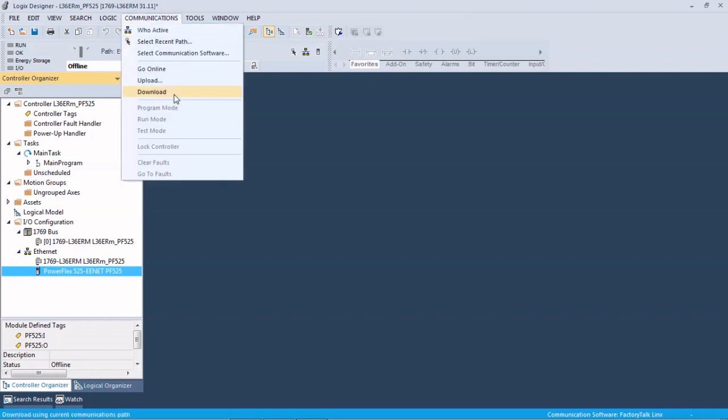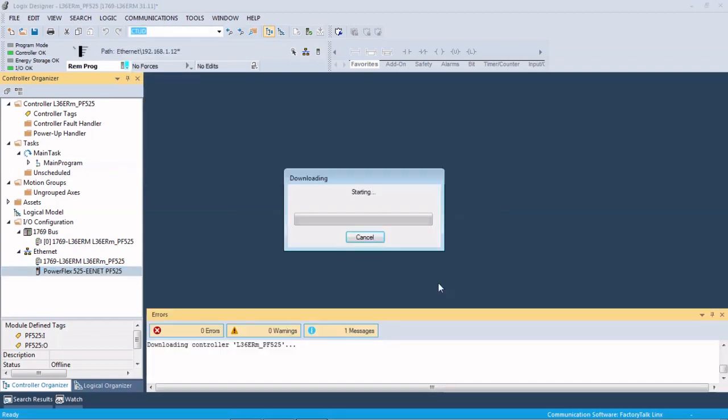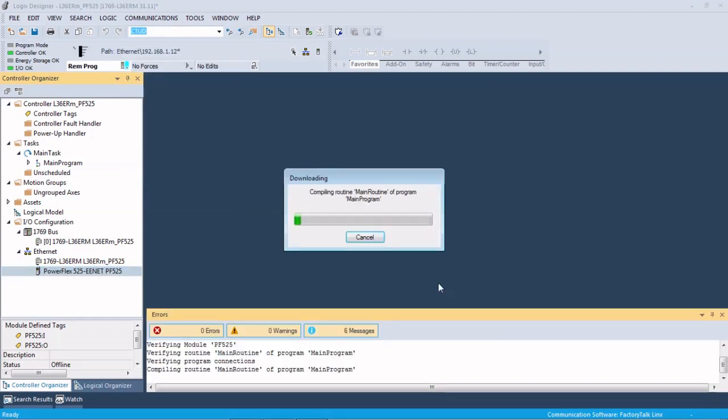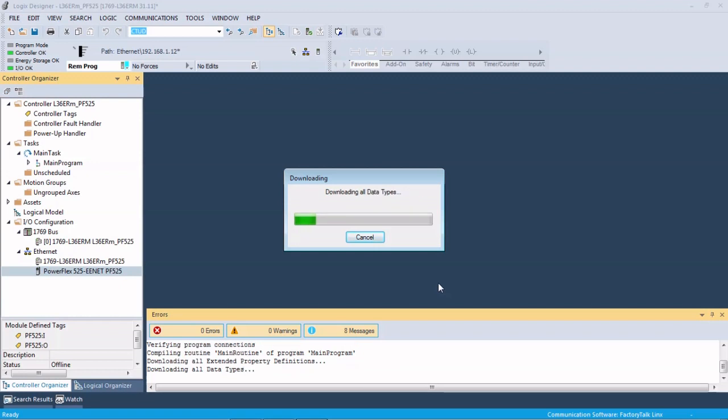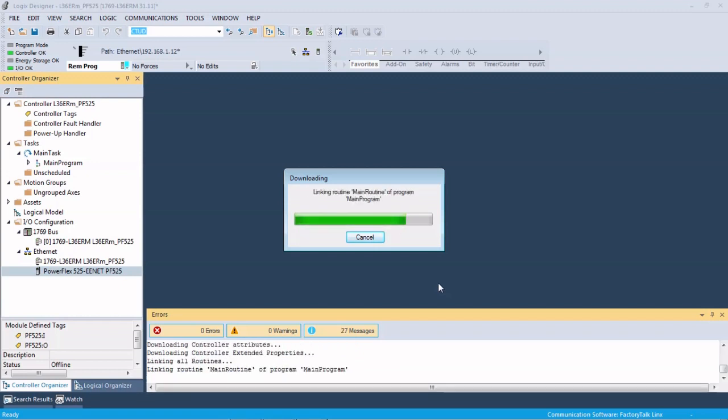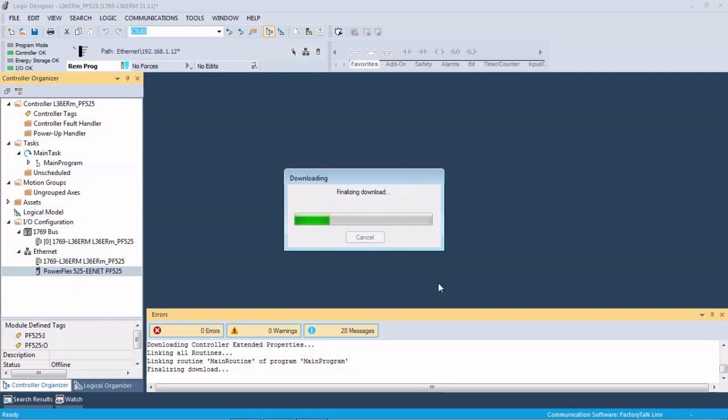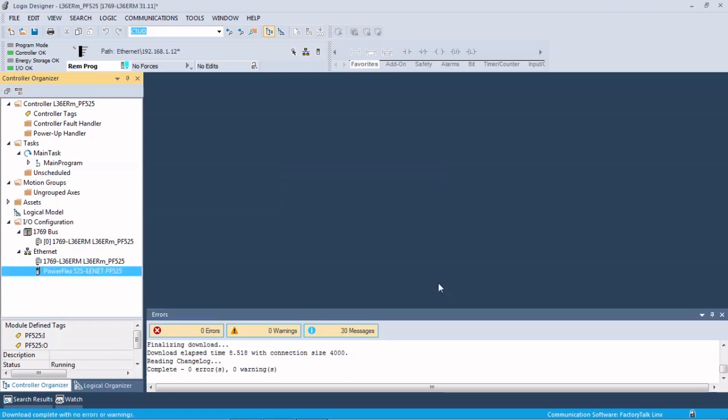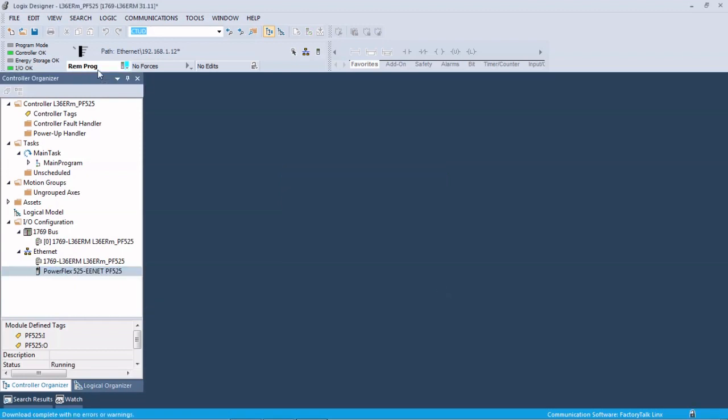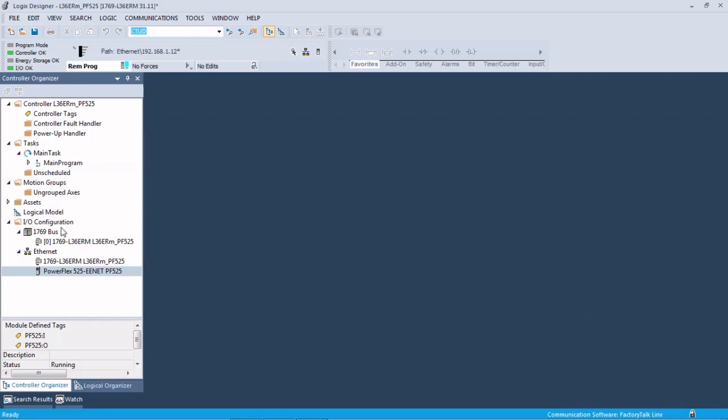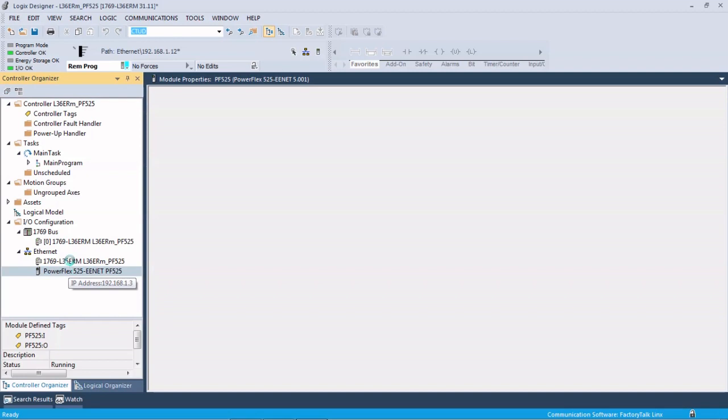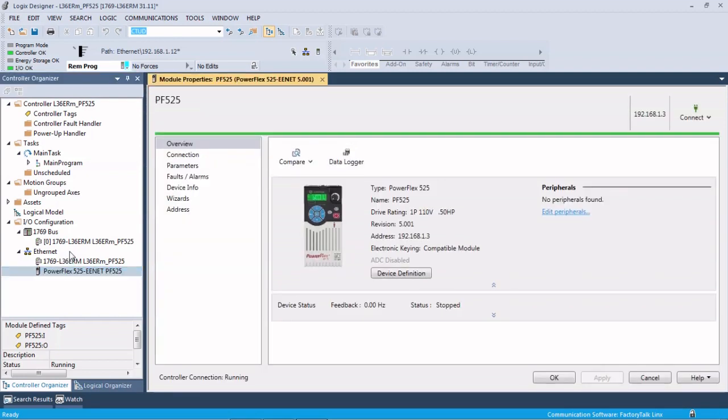We're going to download this to our controller. And when we come online, we're going to leave this in remote program for now so that we can do some autotunes on the drive. If you go to run now, you won't be able to do the autotunes on the drive because the controller will be trying to control the drive, so the drive will ignore you and give you an error. So we're going to leave that in program for now.